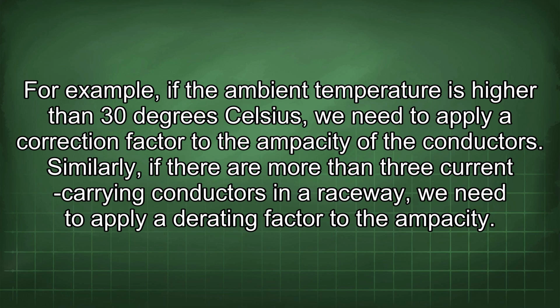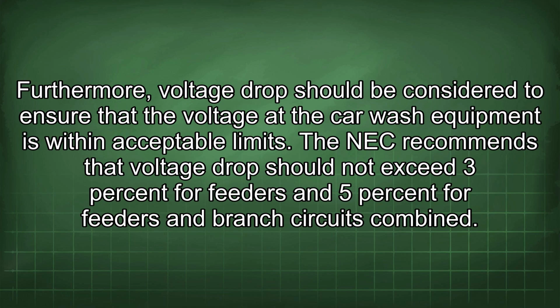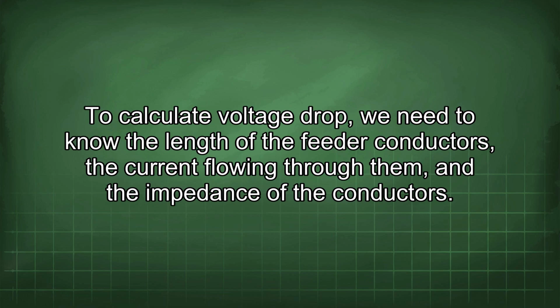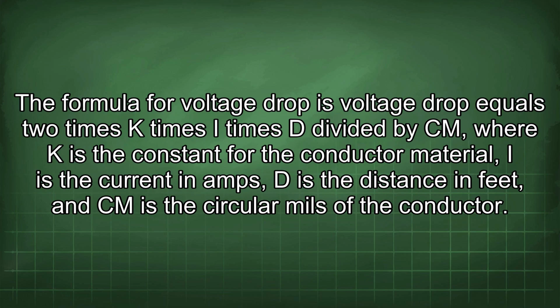to the ampacity. Furthermore, voltage drop should be considered to ensure that the voltage at the car wash equipment is within acceptable limits. The NEC recommends that voltage drop should not exceed 3% for feeders and 5% for feeders and branch circuits combined. To calculate voltage drop, we need to know the length of the feeder conductors, the current flowing through them, and the impedance of the conductors. The formula for voltage drop is: voltage drop equals 2 times K times I times D divided by Cm, where K is the constant for the conductor material, I is the current in amps, D is the distance in feet, and Cm is the circular mils of the conductor.